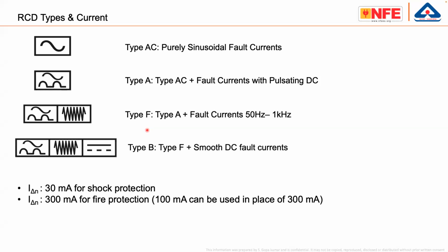And the I delta N, the leakage current, the disconnection current of the RCD: 30 milliampere for shock protection, 300 milliampere for fire protection. Sometimes people say, I will use a 100 milliampere RCD. Yes, of course, you can use a 100 milliampere RCD, but then you should use it in a place where 300 milliampere is demanded. 100 milliampere cannot replace 30 milliampere, but 300, yes.